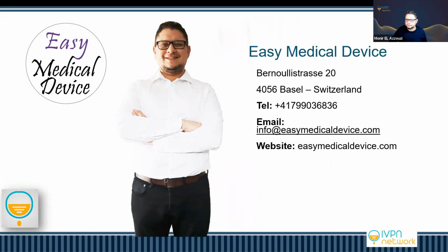Yeah, and if we have a company that is looking for an efficient plan to follow, what are the timelines or deadlines from the European Commission that they need to consider? First, it's not the European Commission that you will be contacting. It's not like in other countries, where you go to the health authority to certify your device. Here you have to contact a notified body. A notified body is a company, and it's really difficult actually, so I will help with understanding that.